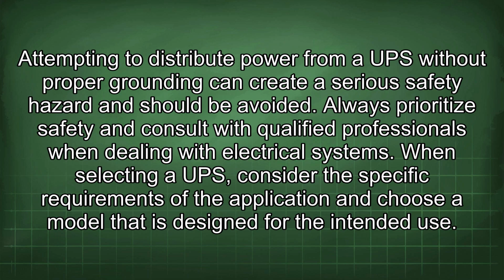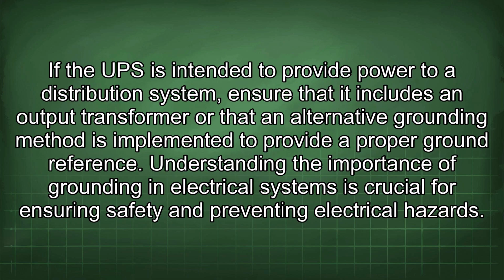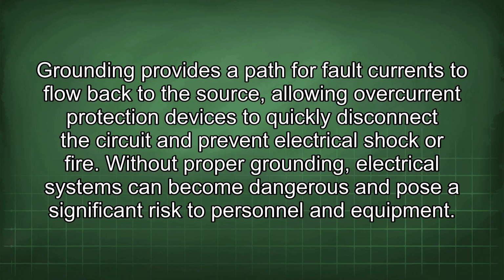When selecting a UPS, consider the specific requirements of the application and choose a model that is designed for the intended use. If the UPS is intended to provide power to a distribution system, ensure that it includes an output transformer or that an alternative grounding method is implemented to provide a proper ground reference. Understanding the importance of grounding in electrical systems is crucial for ensuring safety and preventing electrical hazards. Grounding provides a path for fault currents to flow back to the source, allowing overcurrent protection devices to quickly disconnect the circuit and prevent electrical shock or fire.